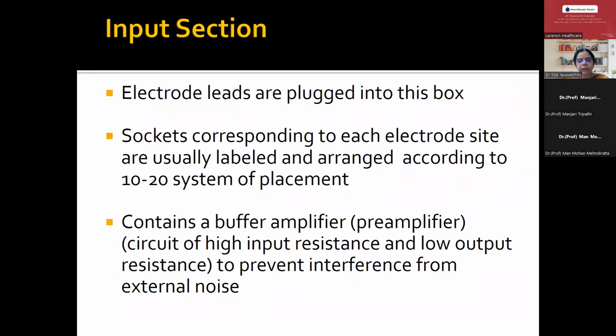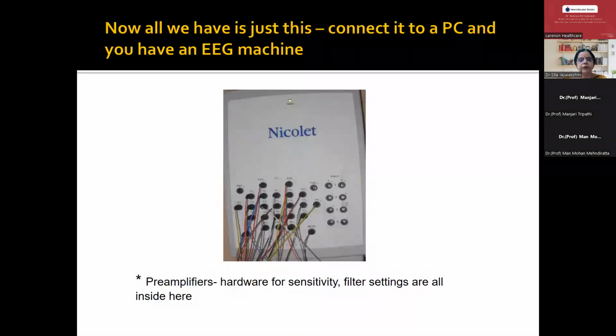So once the electrodes are placed on the skull, we should know about the input section of the head box. The electrodes are plugged into the input section. The sockets corresponding to each electrode site are usually labeled and arranged, and the socket contains the numbers, so it's easy to identify. F3 will go into F3, PZ will go into PZ. It contains a buffer amplifier or preamplifier to prevent interference from external noise. So this is a preamplifier, which connects to the PC, and it is very handheld and you can carry it anywhere you want carefully.